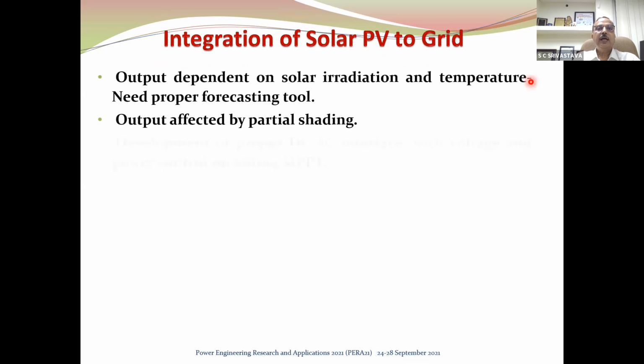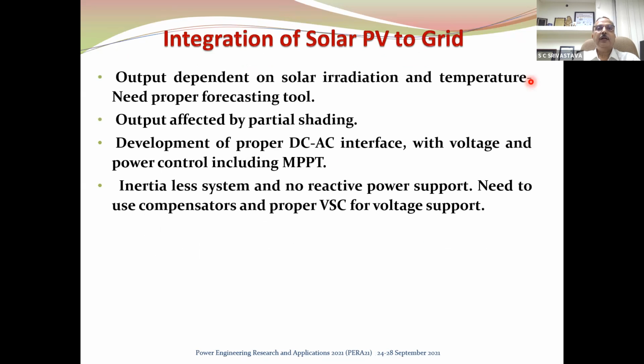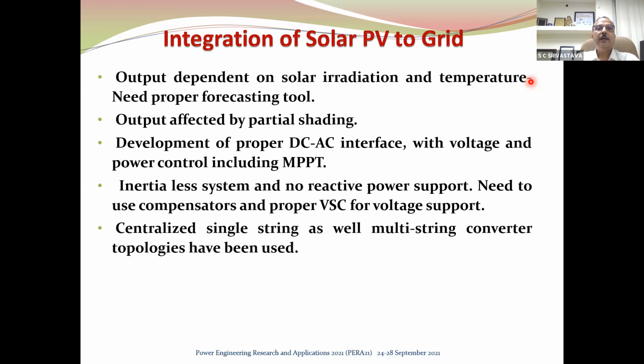Now coming to solar quickly - its output depends on solar irradiation and temperature, so again it needs very good forecasting. One important tool required in managing renewables is accurate forecasting. Partial shading problems occur when partial cloud cover is present. Since solar is a DC source, integrating it to the AC system requires a DC-AC interface with voltage and power control, ensuring maximum power tracking. It has no inertia and no reactive power support.